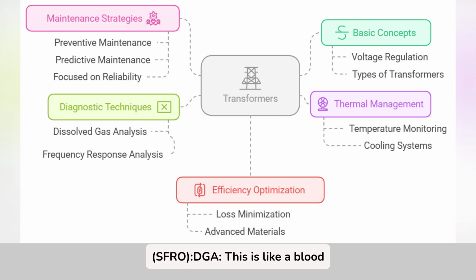DGA is like a blood test for the transformer. It detects gases in the insulating oil that indicate possible internal faults. SFRA is similar to an ultrasound scan; it evaluates the mechanical integrity of the windings and core, detecting deformation or damage.